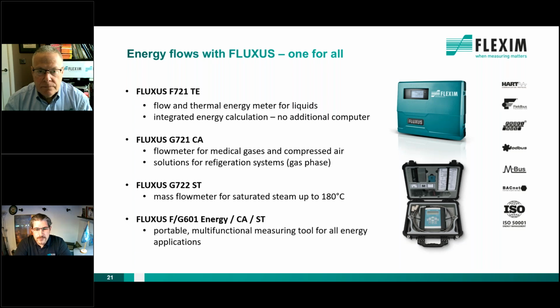And very importantly, all of this with, again, the same measuring principle is available as a portable meter. You can see it in the picture here, at the bottom right-hand, this carrying case. This is a battery-powered handheld portable meter that you can use for all of these applications, so that you have really a multi-tool in your hand that you can carry around your estates and check your energy flows, your oxygen flows, your steam flows, everything integrated in this one meter. You would just need the right transducer for different applications, but basically you have a very powerful multi-tool which you can use to determine energy flows in areas where you do not want to install a fixed meter, where it probably is not necessary, where it's good to have to check it once a year or once every half a year.